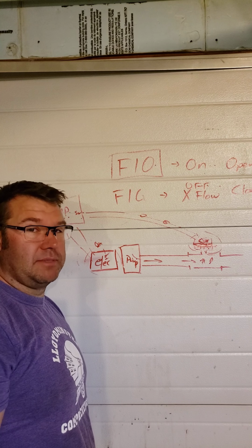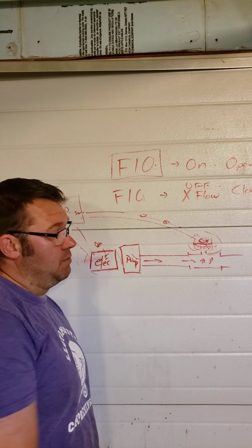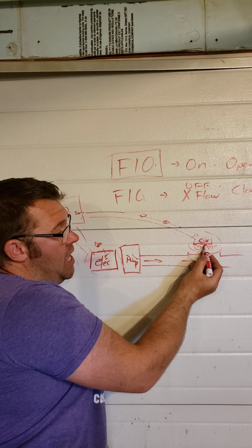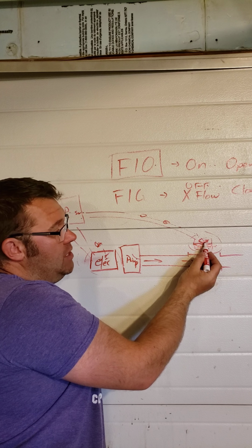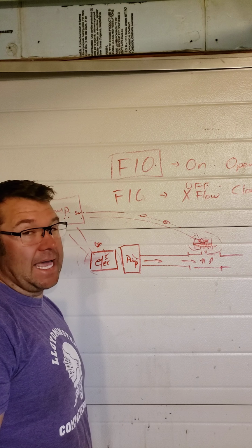Sometimes it works, sometimes it doesn't. So I'm guessing that very likely it's just an adjustment where I need to back that screw out, take away some spring pressure, allow that diaphragm to push up easier, and close that switch. Okay, so I'm guessing that's likely the issue.